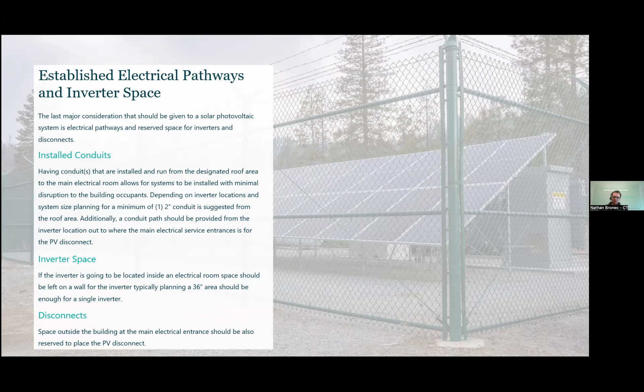Same thing with outside the building. Most of our utilities here in Montana and across the Northwest that I've run into all require that visible disconnecting means outside the building for the PV system. And with that, you're looking at the building entrance where the meters are and stuff, and sometimes that's a really congested area too. So trying to make sure to have that PV disconnect slated out there and a room accommodating it is another important piece that we often run into when we're trying to retrofit existing buildings with solar.